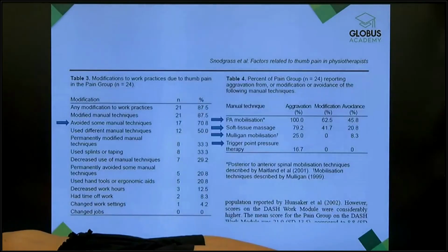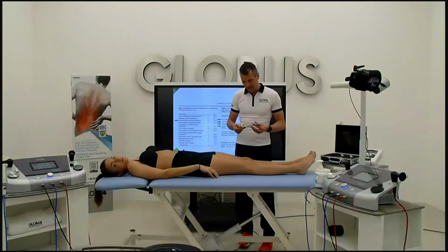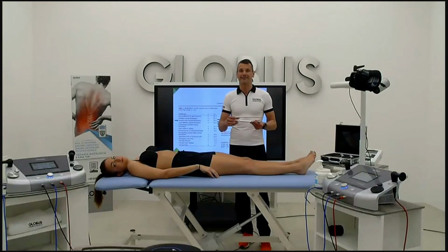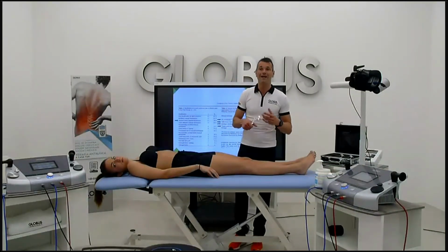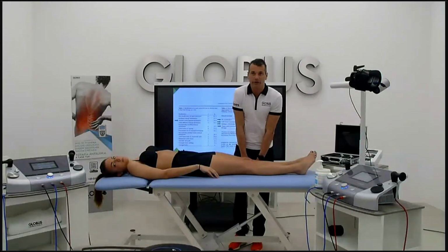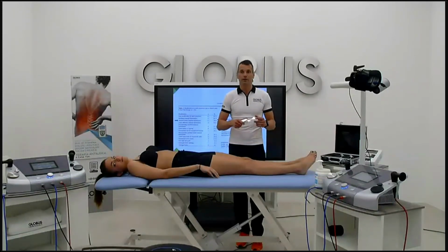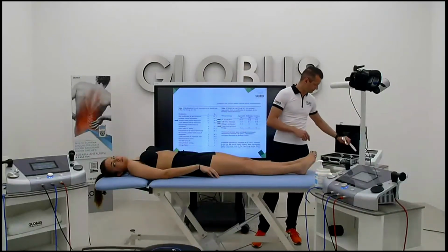One thing about this is talking about how much energy we can save. By using the tool, actually you save 4 to 5 times your force, your energy. So it means that by pushing just 200 grams, you achieve 1 kilo of force on tissue. So we don't need to push great levels of energy, but just very gentle forces for achieving a force 4 to 5 times higher.